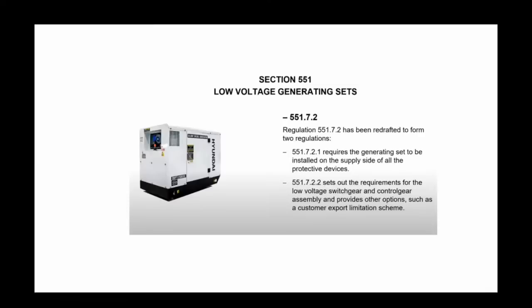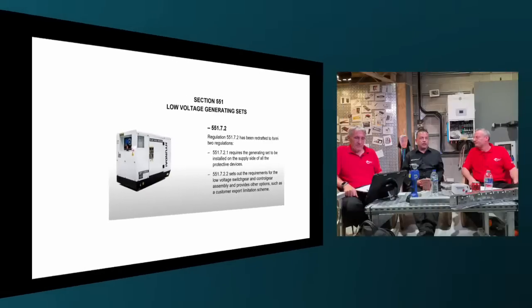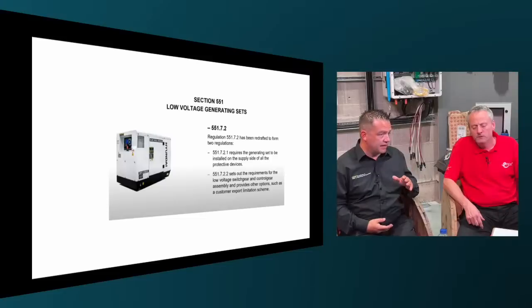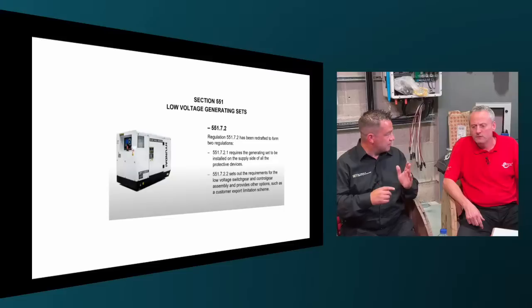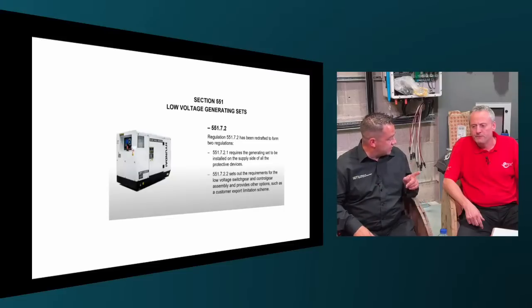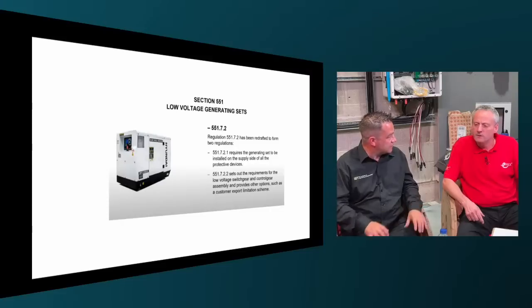551.7.2. Well, before we get into this, we'll just touch on 551.7.1, if that's okay. There's been a couple of changes there. So the first change is it's no longer acceptable to supply a low voltage generating set by a split load board. So if you've got a split load RCD, you can't use a split load RCD whatsoever. And the reason for that is if you get a fault and the RCD trips, the theory is that the PV inverter could still be supplying the other circuits on that RCD and the split load board.